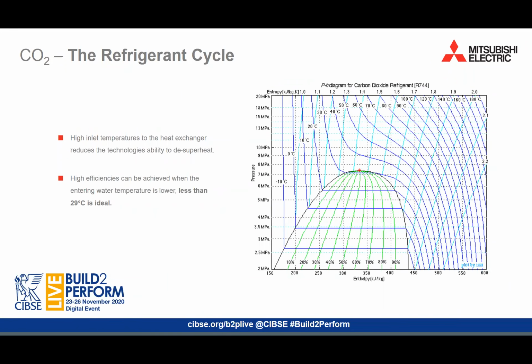So let's take a closer look at what this looks like on a pH diagram. The diagram on this slide is describing the relationship between pressure, temperature, and enthalpy of CO2. The critical point is marked by the red cross. Point 1 on this graph is the point at which the refrigerant enters into the compressor. The effect of the inverter scroll compressor increases pressure from approximately 40 bar to 120 bar and increases temperature from approximately 10 degrees Celsius to 110 degrees Celsius. At the discharge of the compressor, the refrigerant has a huge amount of stored thermal energy.